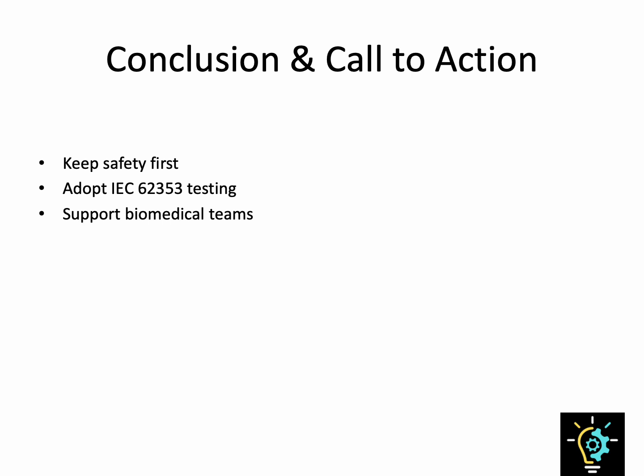To wrap up this video, IEC 62353 is more than a technical standard. It's a philosophy of safe, practical, and efficient in-service testing. It makes sure the devices remain working throughout their life. And for biomedical engineers, clinical technicians, and manufacturers, adopting IEC 62353 means fewer risks, clearer results, and a consistent framework to rely on. So the call to action is simple. Embrace IEC 62353 as part of your maintenance routine. Use the right equipment, document thoroughly. You'll actively protect patients, staff, and the integrity of medical technology itself.